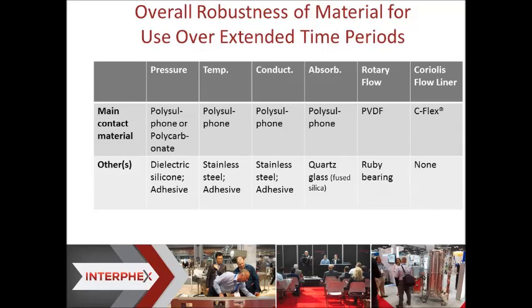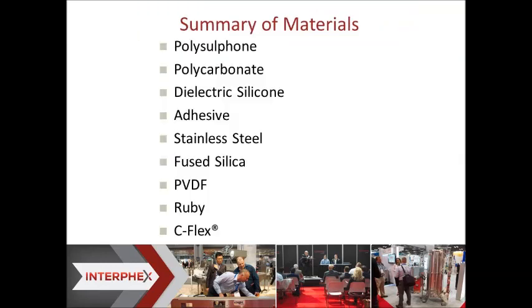So across the bottom row are the other materials used in the sensor. Pressure has a dielectric silicone as well as an adhesive. Temperature and conductivity have a stainless steel component as well as adhesive, and the others there are listed. So just take, again, a high-level view at looking at this. Here's a summary of the materials that would need to be able to sustain long-term exposure in a process.